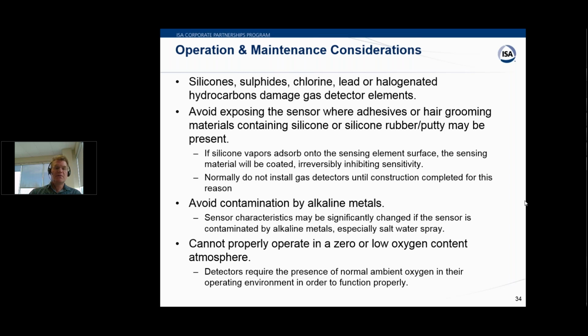Okay, so just some things to really be aware of. Almost all gas detectors are sensitive to silicone, sulfides, chloride, halogenated hydrocarbons. This is why we do not normally install our gas detectors until construction is completed, because guys are putting silicone seals around the building, all that kind of stuff, and you poison your sensor. So avoid contamination. Just be aware of these things when you're working. And if all of a sudden your detector goes wonky, it might just be because someone was doing some work nearby and put a dab of silicone, and it got into your detector.